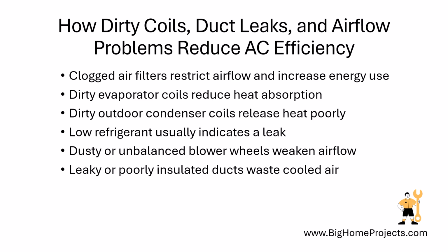A damaged blower wheel may collect dust or become unbalanced, reducing the amount of air pushed through the rooms. Leaky or poorly insulated ducts can lose cooled air inside an attic, crawl space, or wall before it reaches the living area. One detail many people miss is that a frozen indoor coil can be caused by restricted airflow, not only by low refrigerant, and running the system while it is frozen can cause more damage.